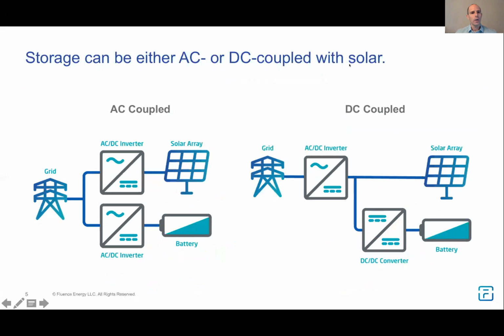As touched on briefly earlier, storage can be either AC coupled or DC coupled with the solar. This is a cartoon drawing, a sort of cartoon one-line diagram, of those two options. On the left is AC coupling, where both the solar and the battery have their own dedicated inverters and connect at some point further up toward the grid. As alluded to earlier, where exactly that connection point is can vary—you could have both connect at high voltage, or at medium voltage with only a single transformer between medium voltage and the grid. The main takeaway is that the solar and the battery each have their own inverter converting DC sources into AC.